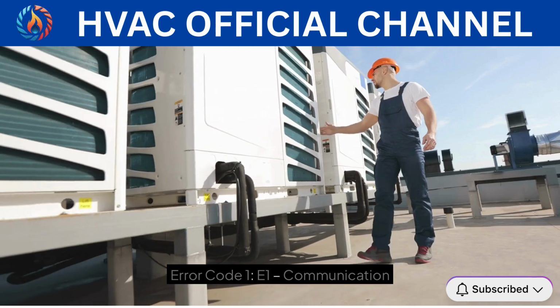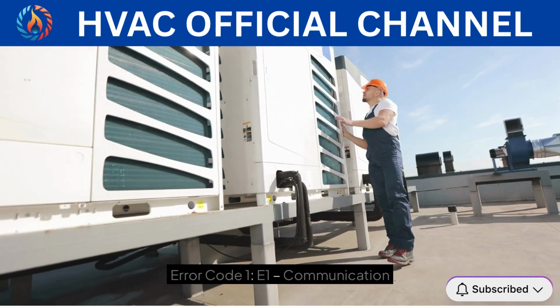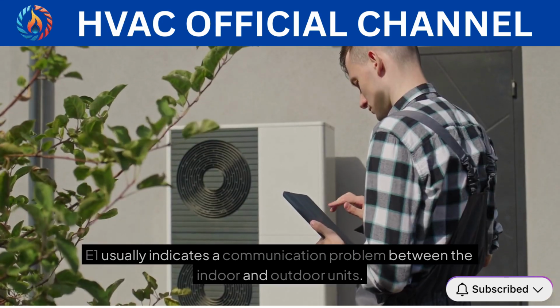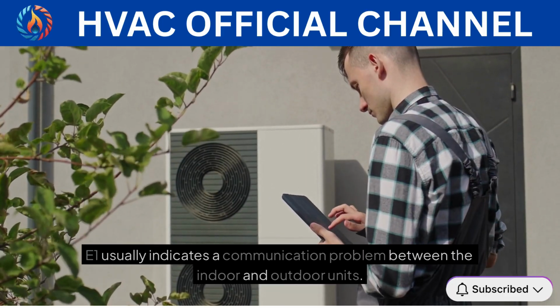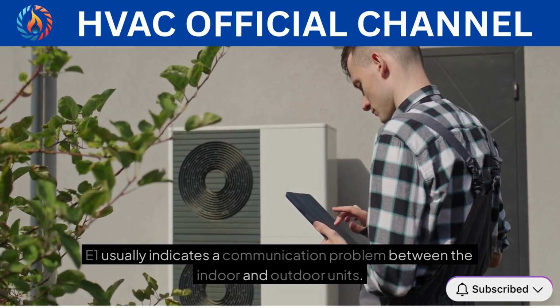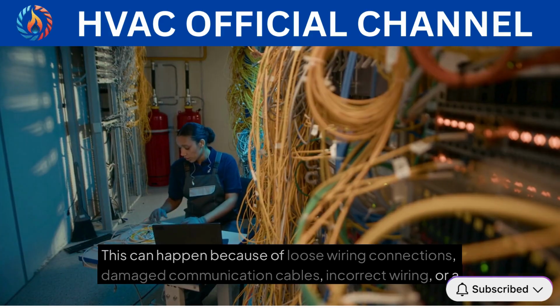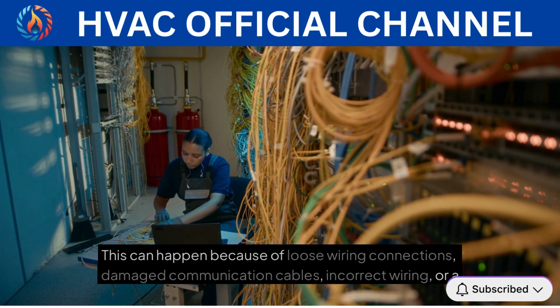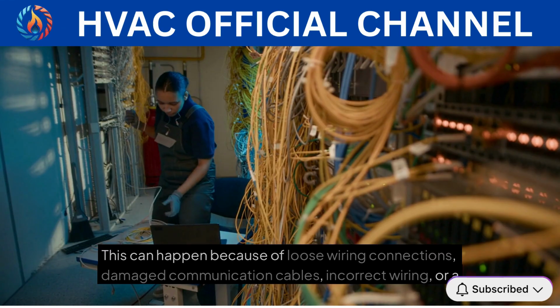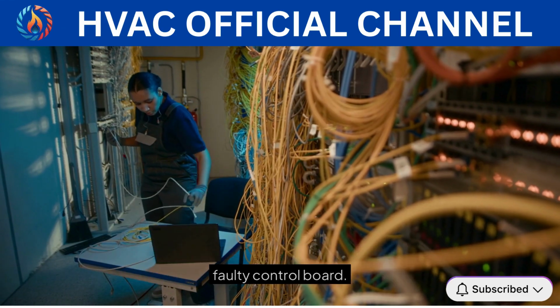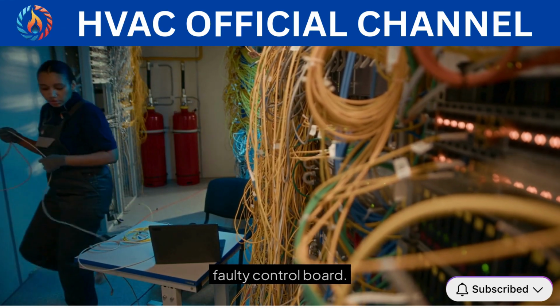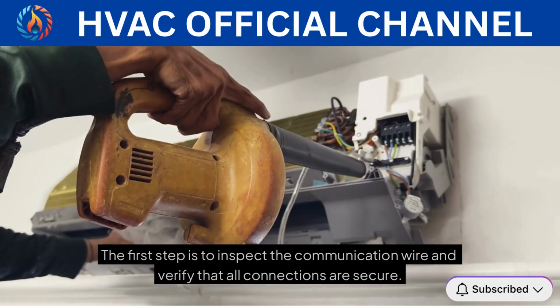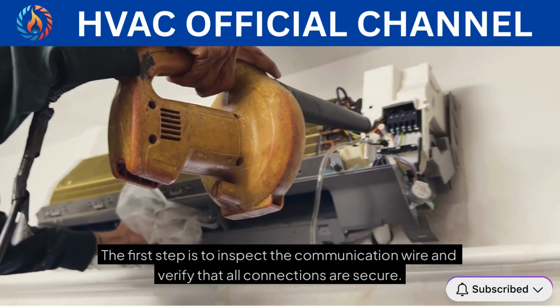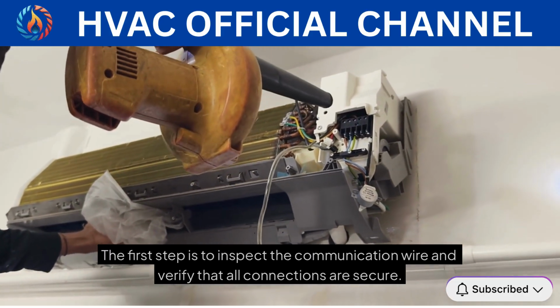used by many manufacturers. Error code 1, E1, communication error. E1 usually indicates a communication problem between the indoor and outdoor units. This can happen because of loose wiring connections, damaged communication cables, incorrect wiring, or a faulty control board. The first step is to inspect the communication wire and verify that all connections are secure.